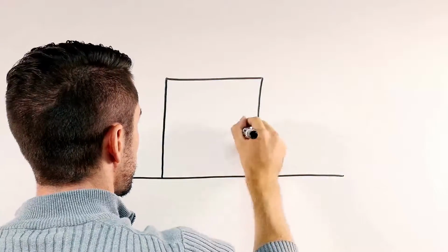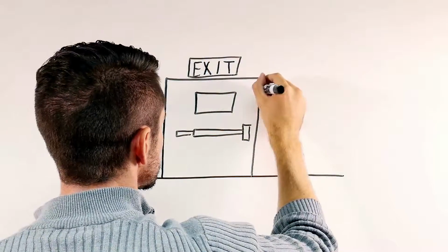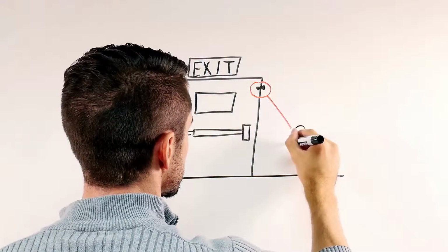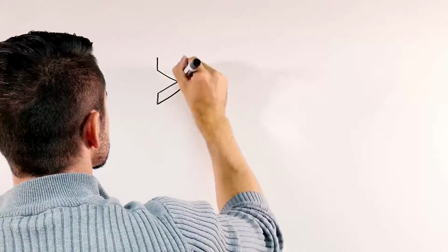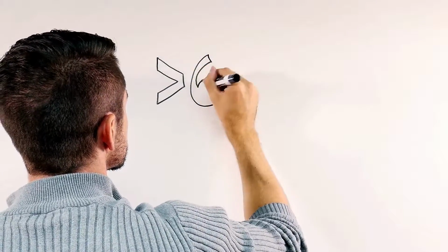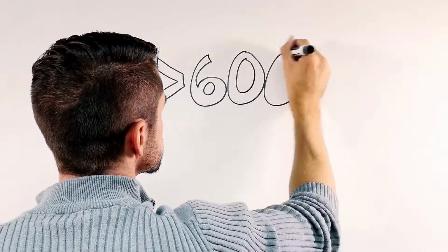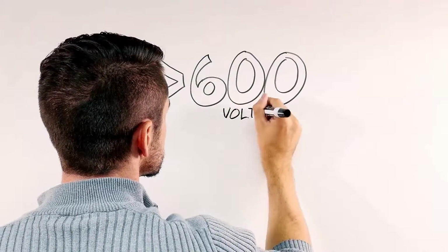Code requirements typically prohibit the installation of any other type of lock on a door with panic hardware, with the exception of electromagnetic locks released by a sensor or by a switch in the panic hardware. Some rooms containing electrical equipment are required to have panic hardware or fire exit hardware to allow a technician to escape if there is a fire or explosion.